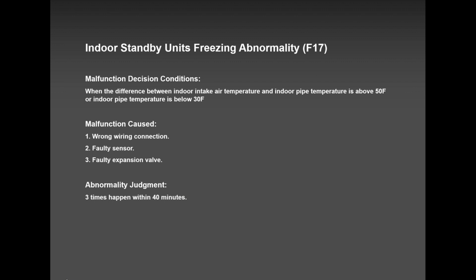So please guys, keep in mind that when you cross the wires in winter time, you may not encounter any problems. But the moment you switch over to cooling, the problems will come up and they will call you. So F17 and H39 are error codes related to cross wiring. Unit A went to B, B went to A. You will not get these error codes on a single zone.